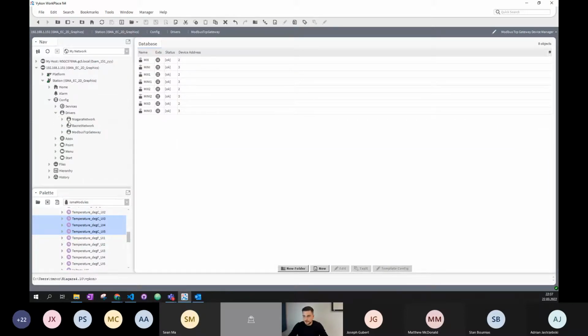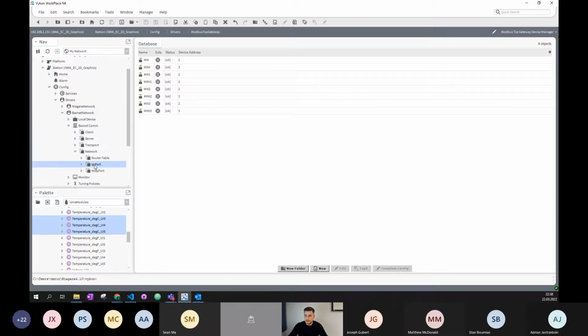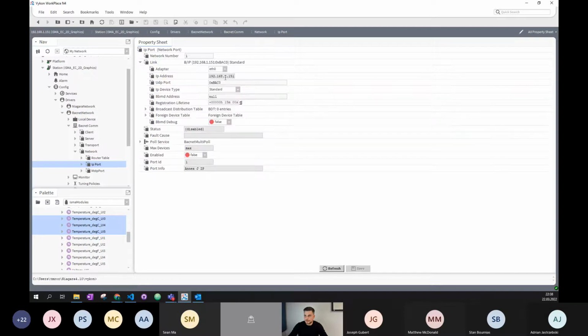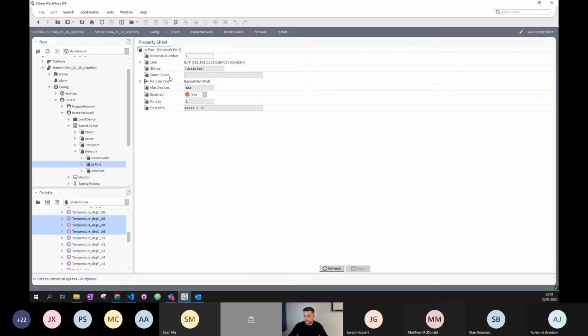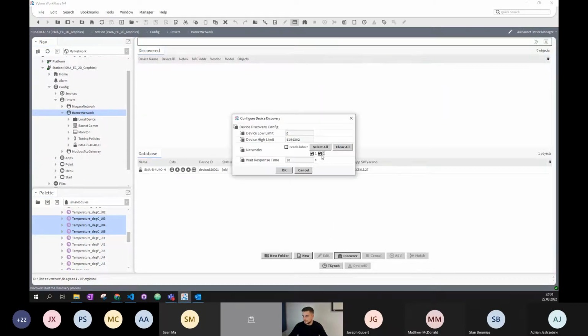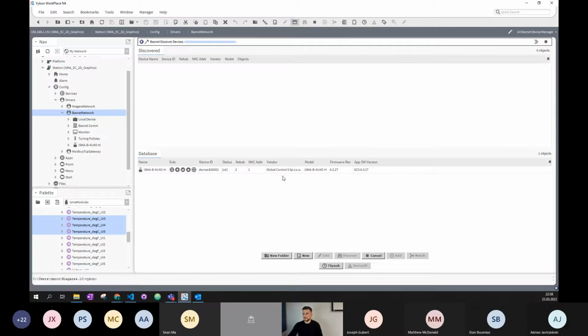One more thing before we finish this section: it's also perfectly fine to use Modbus TCP and BACnet IP at the same time to integrate data from this IP module. If we go to the BACnet network, we first need to enable the IP port. So here I have my IP port enabled, and now I can go to BACnet and discover the devices. I will search network number 1, because network 2 is BACnet MSTP, which I don't want to search. So the discovery process is ongoing.